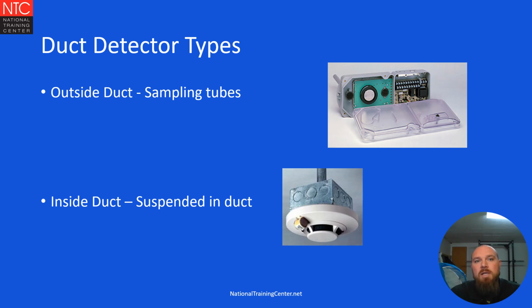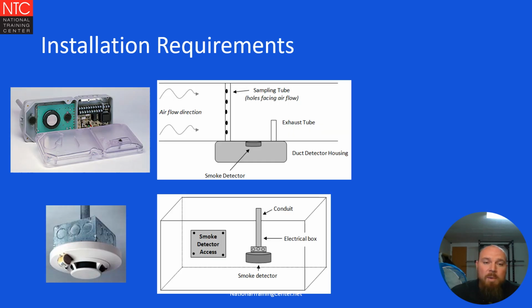Now, with your duct detectors, you have two very common types of detectors. You have your outside duct detector, which will have a sampling tube, and you have your in-duct smoke detector. Your in-duct smoke detector is most times going to be suspended within the ductwork itself. The installation requirements with these detectors depend on which ones you're using.